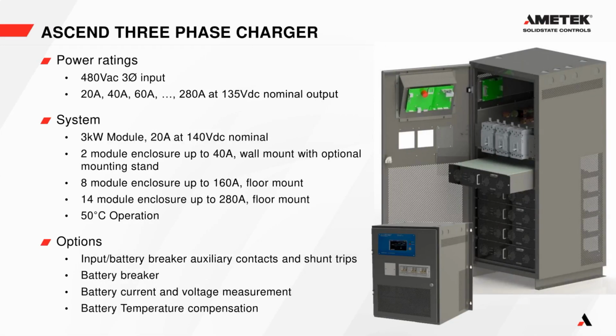So about the Ascend 3-phase charger, it is a 480 volt 3-phase input modular charger. We offer sizes of between 20 amps and 280 amp outputs with intervals of every 20 amps. So each module is a 20 amp module at 135 volts DC. And we can stack up to 14 of those together. So like I said, the 20 amp module's total output power is 3 kilowatts.